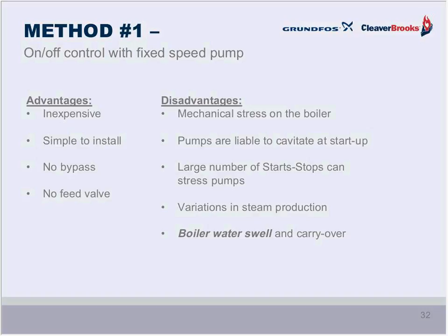The number of starts and stops per hour can vary, but it can range in that 6 or 8 starts and stops per hour. You get variations in steam production, and there's something called boiler water swell and carryover. Basically, that is when water gets mixed in with the steam that goes out into the distribution system, and when that happens, bad things happen in the system, as Steve indicated earlier.